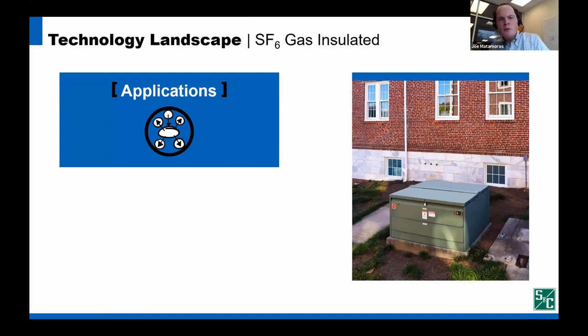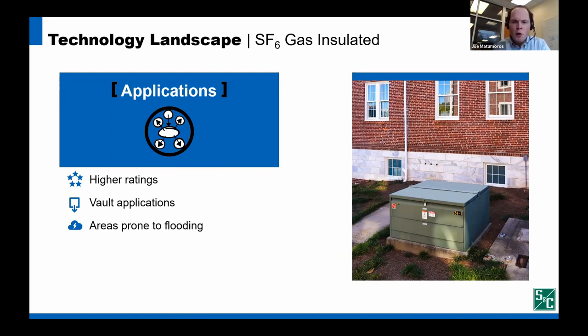So let's view some more of the applications where gas insulated gear is applied. It's applied where higher voltages and higher interrupting ratings are needed, for example, 38 kV and 25 kA applications. It's applied in below grade applications like an urban vault, underground vaults, and in areas that are prone to flooding.